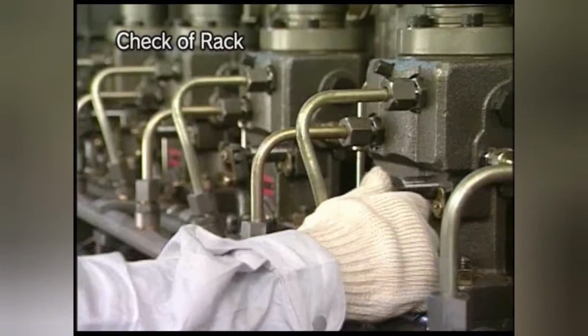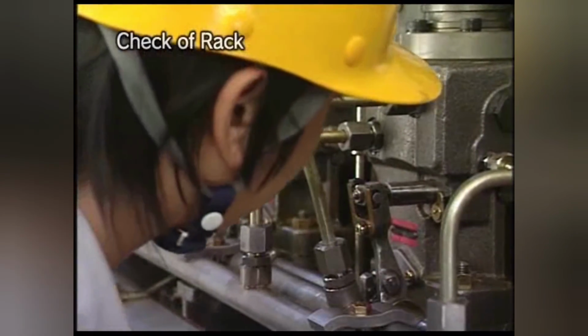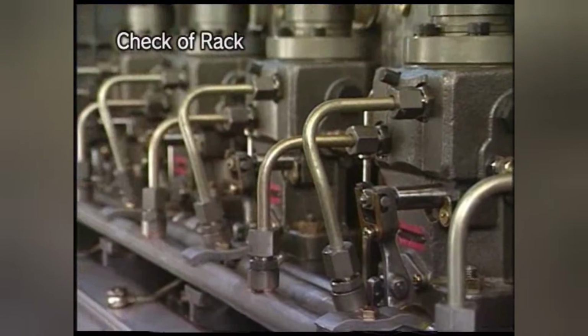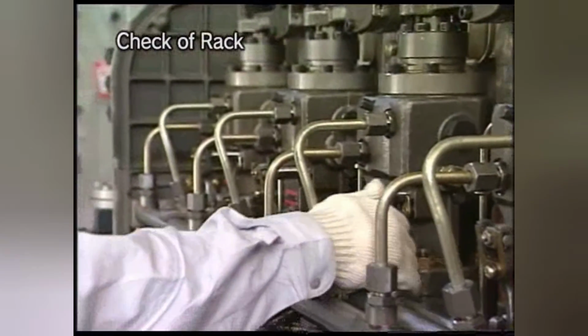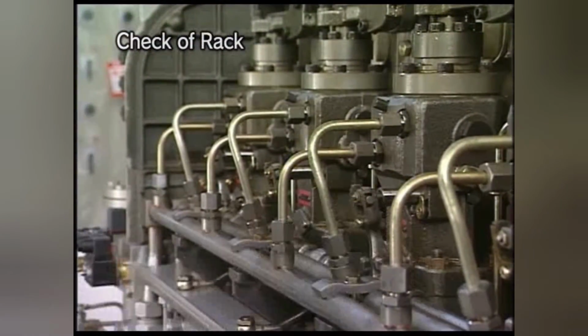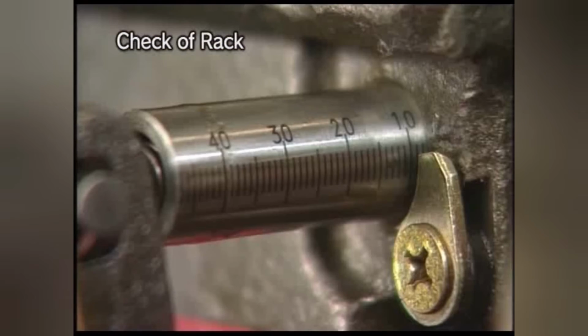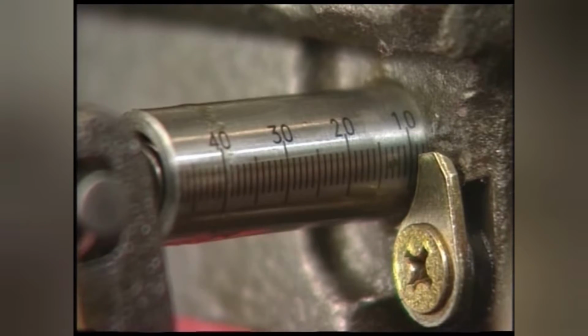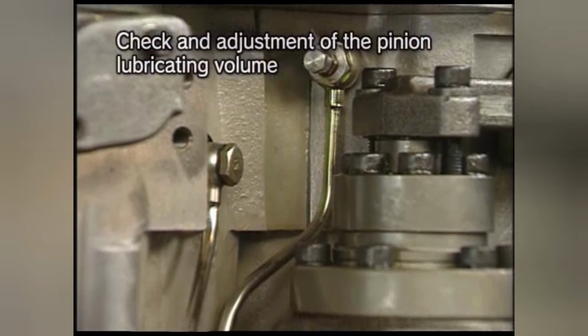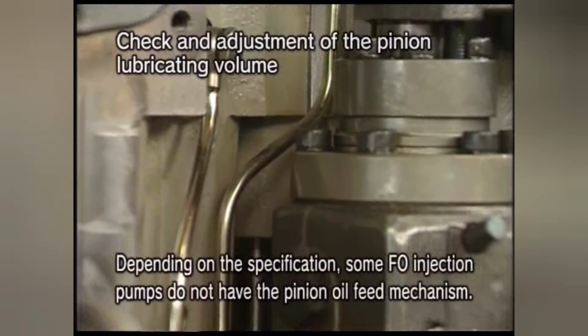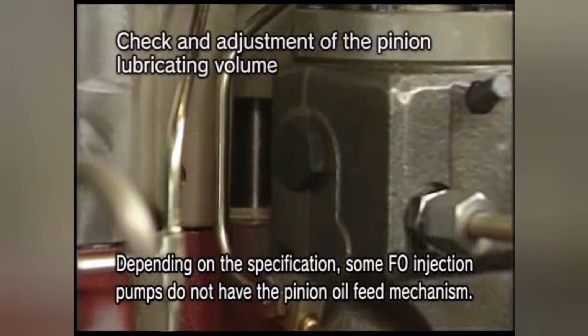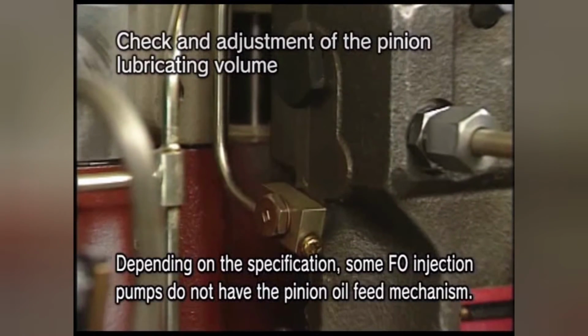First, remove the pump cover to check if the rack has not got stuck. Also, check the position to see if the graduation doesn't vary widely between cylinders. For HFO specification, lube oil is fed into the pinion sleeve of the fuel injection pump, so check about it.